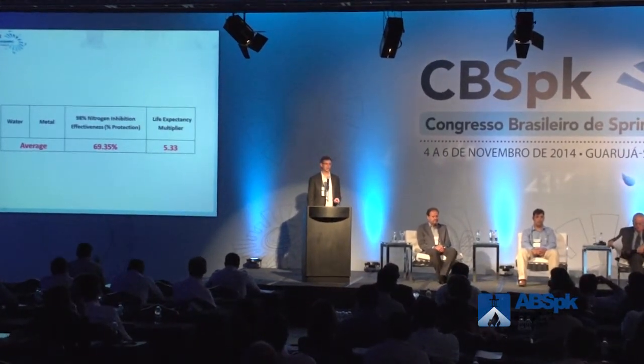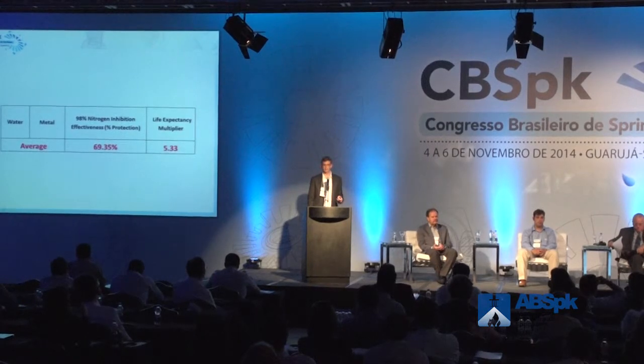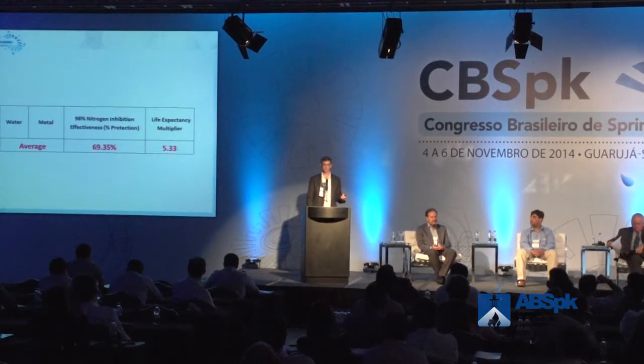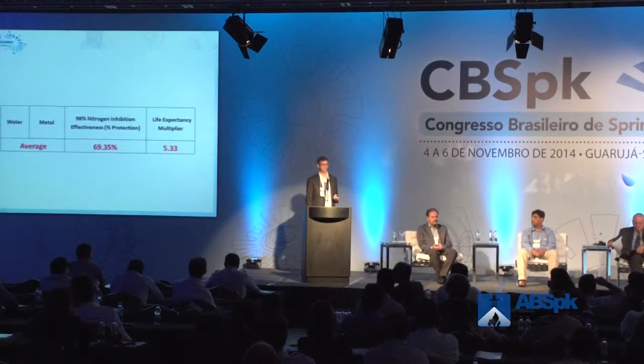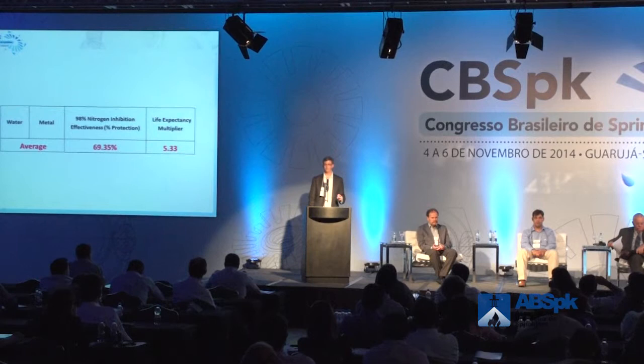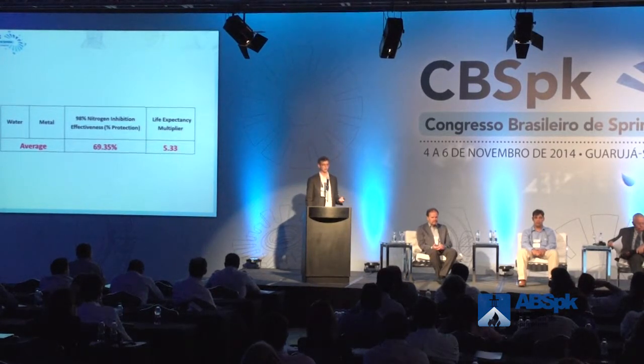So we got a series of data out of running this test, and what we wanted to look at was the effectiveness for the customer of using nitrogen over compressed air in a fire sprinkler system. What we found is, under a variety of different conditions, it reduced the corrosion rate quite significantly. You get a life expectancy increase in that fire protection system of about 5 times. So instead of a system that would last 10 to 15 years before a contractor has to go in and replace pipe, you're looking at more like 50 to 75 years of operation, with little maintenance.